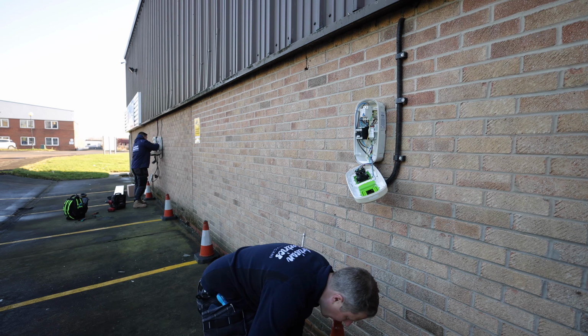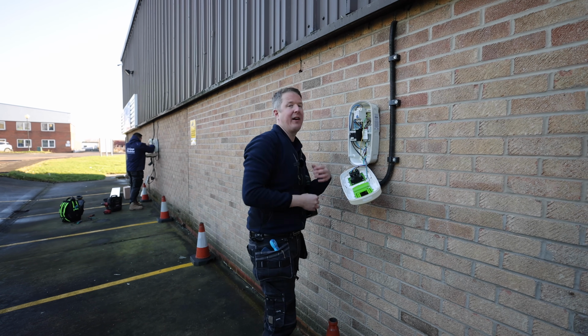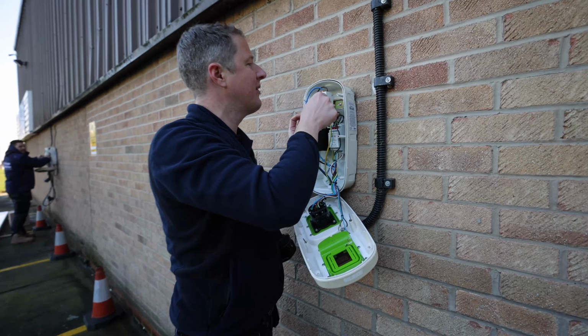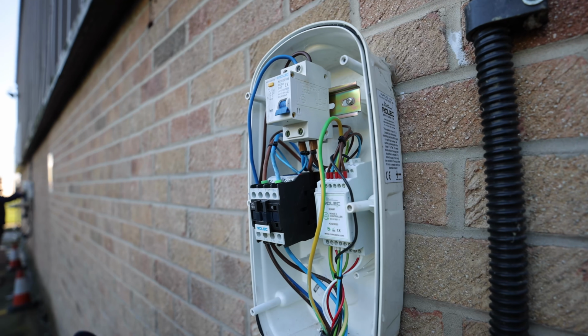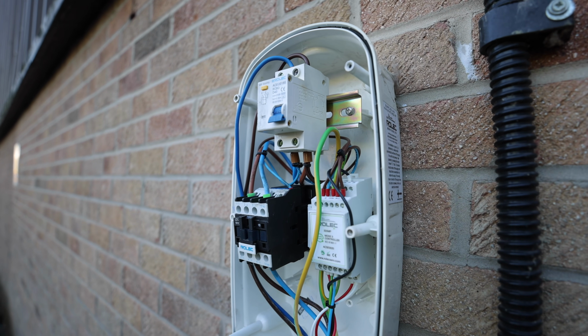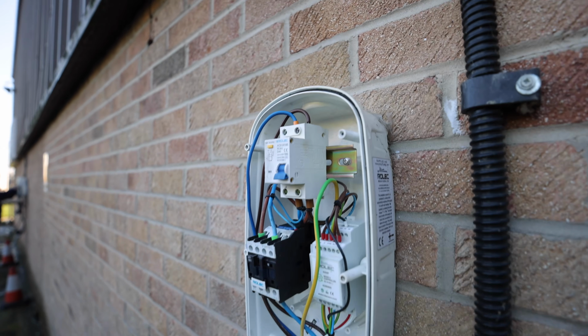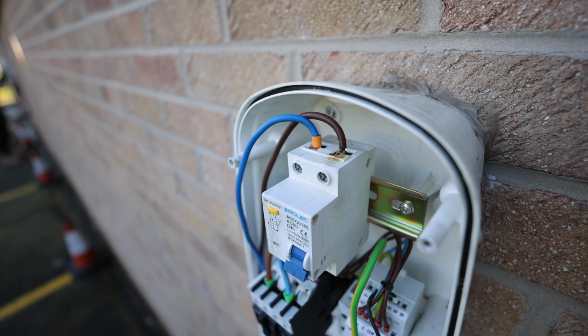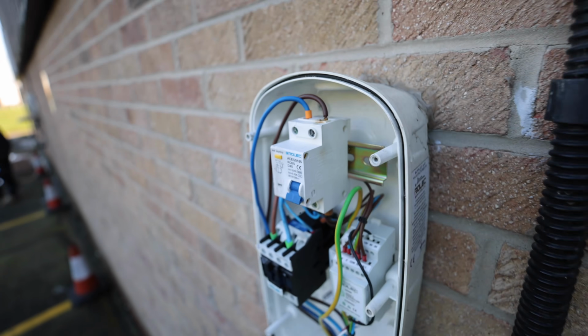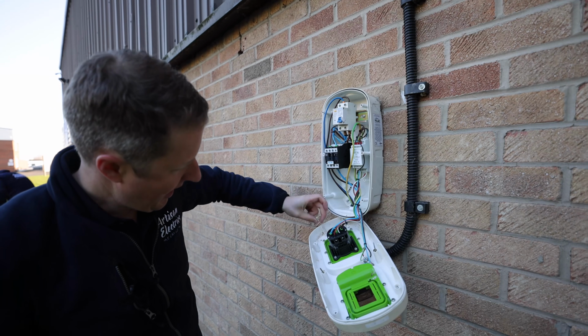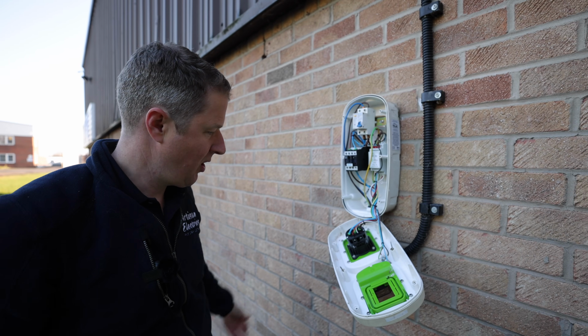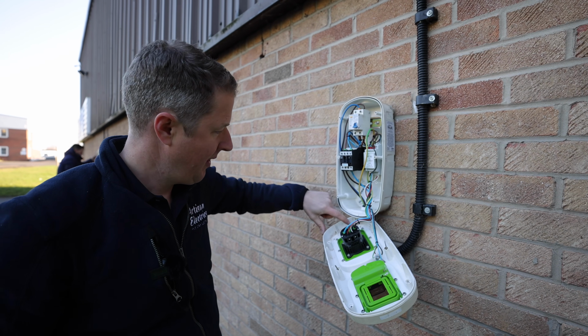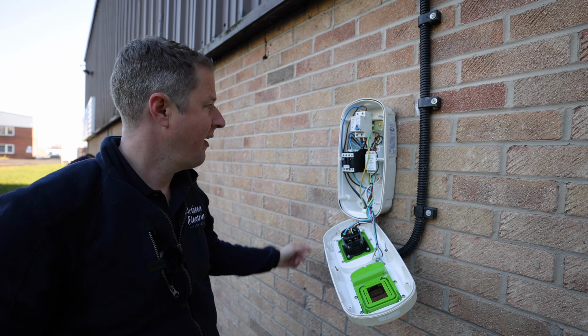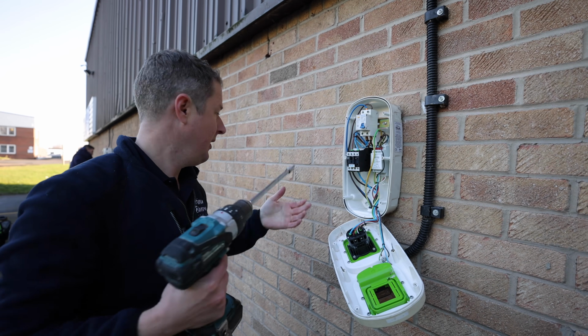Got the old proving unit on, but check this out guys, look at the burnage on this. This happens a lot with these Rolec units, I've shown it in another video. Burning on the top of the RCD there, the conductor's just overheated. The whole thing, some of the screws weren't fitted properly, so they've got a bit of water in them. They're just a bit of a mess, so gonna rip them out.